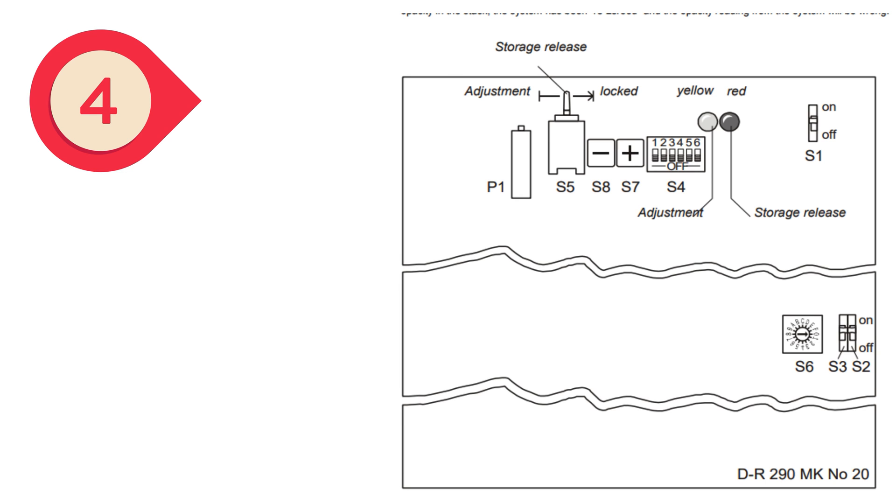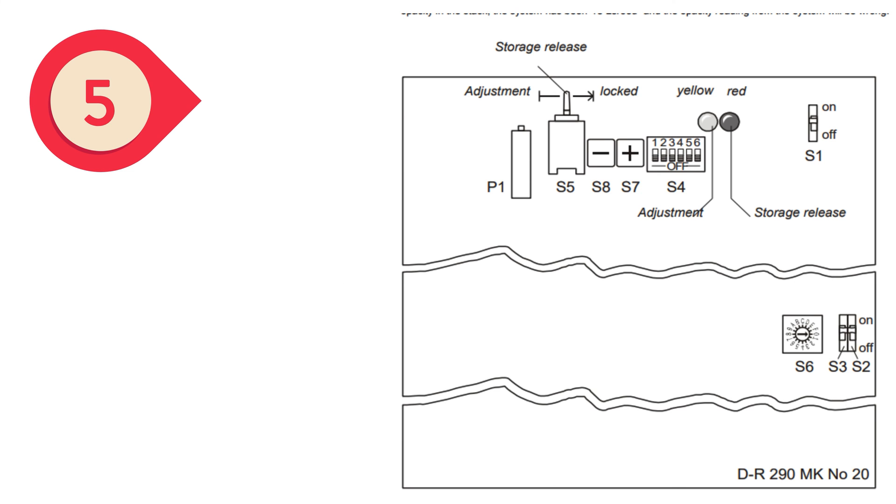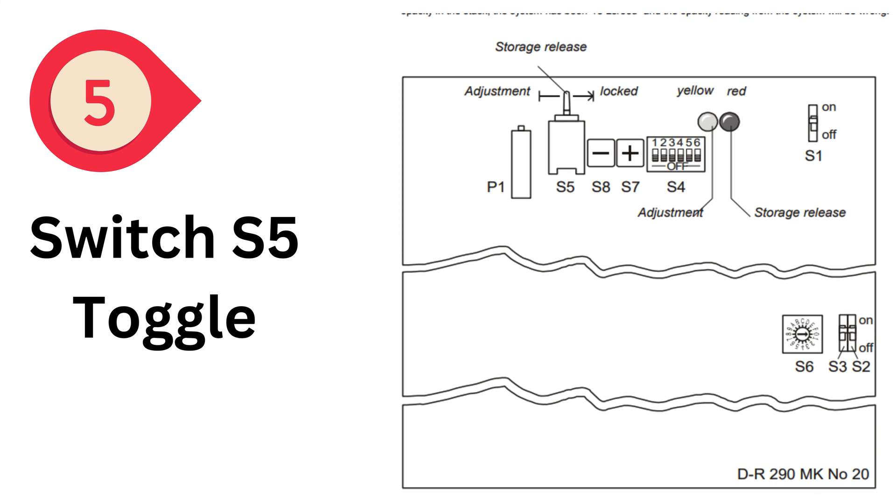Step four: Put switch S3 calibration function to the on position. Step five: Toggle switch S5 must be set to free memory access so that the red LED lights. The first line of the display should alternate between offset plus and window check.